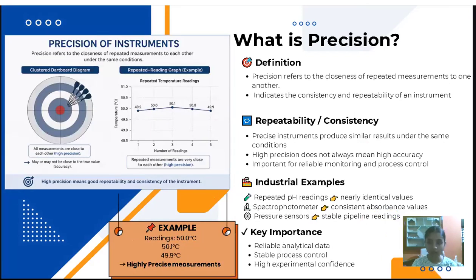Now, what is precision? Precision describes the consistency of repeated measurements. Consider if an instrument gives nearly the same reading every time under identical condition, it is considered precise. For example, if a sensor repeatedly displays values such as 49.9 degrees Celsius, 50.1 degrees Celsius, or even 50 degrees Celsius, the measurements are highly precise because they are closely grouped together. However, the readings may still not match the true value, meaning an instrument can be precise without being accurate. In analytical instrumentation, precision is important for obtaining reliable and reproducible experimental results.